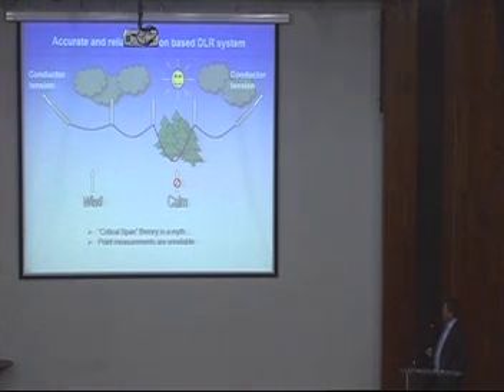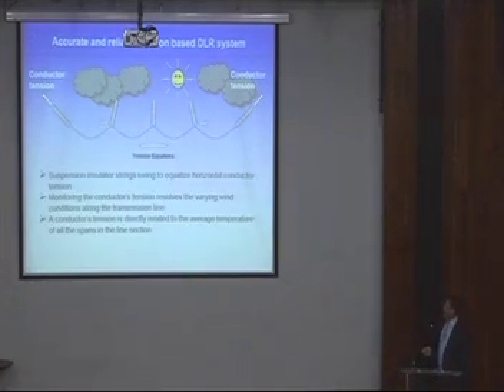So this part of a conductor will elongate and sag, as I showed at the beginning. But the line design, especially this design with these insulator strings, is exactly causing a movement and equalization in the section. What happens in that case is that the tensions are not in equilibrium at this point, so that causes these insulators to swing in a certain direction, and at the end you have this constant horizontal tension along the whole section.